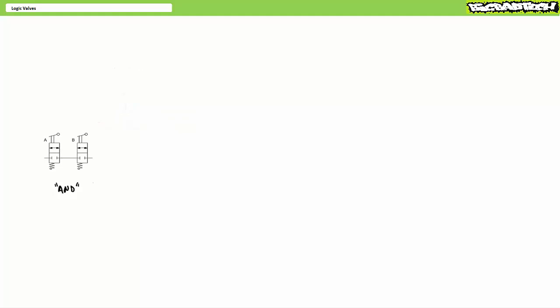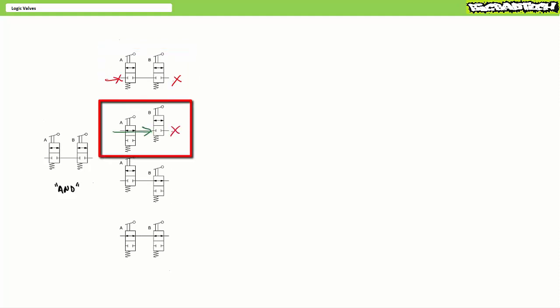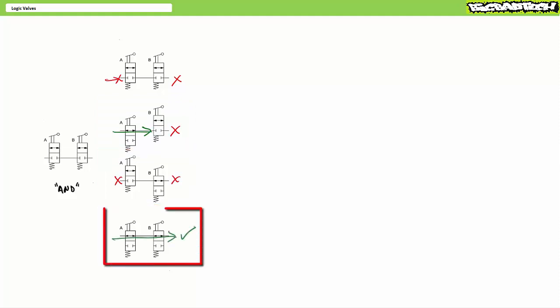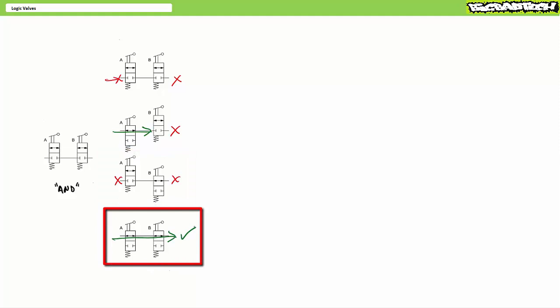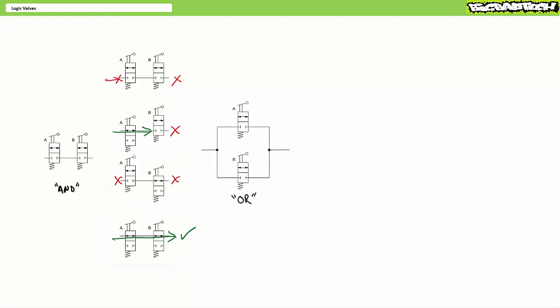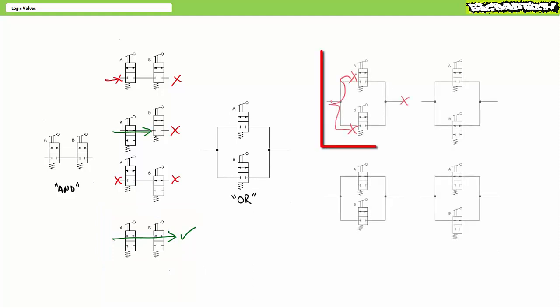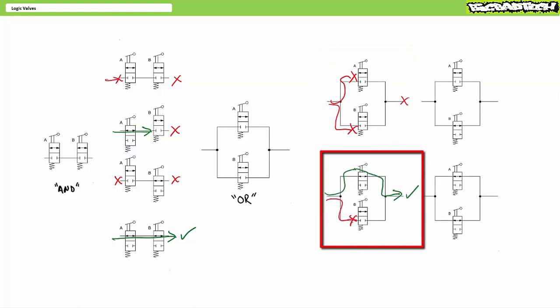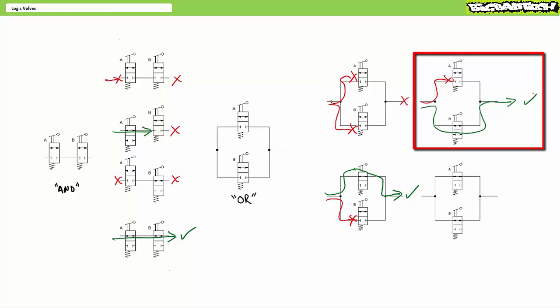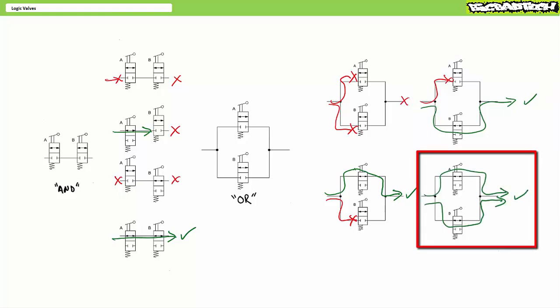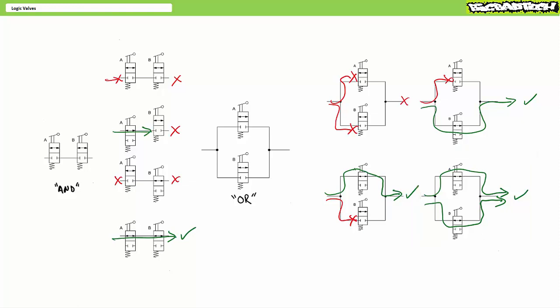There are alternative methods to implementing logical or decision-making functions in air-piloted pneumatic systems, but they aren't nearly as clean or easy to implement as logic valves. For example, one could rig up an AND function using a series connection of two normally closed valves — both must be open to get output. Similarly, one could rig up an OR function using a parallel connection of two normally closed valves — either open gives output. However, these systems are messy, and in the parallel OR configuration when both valves are open, they allow undesirable reverse passage: A into B and B into A.